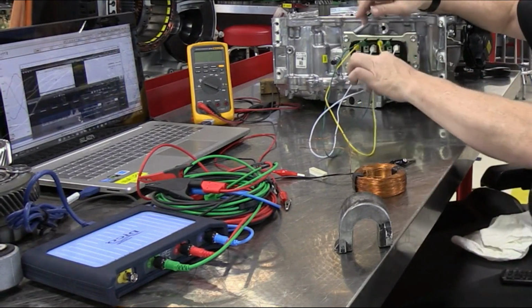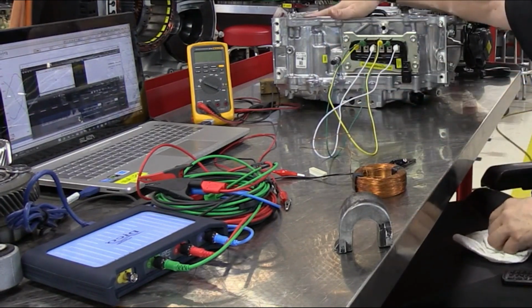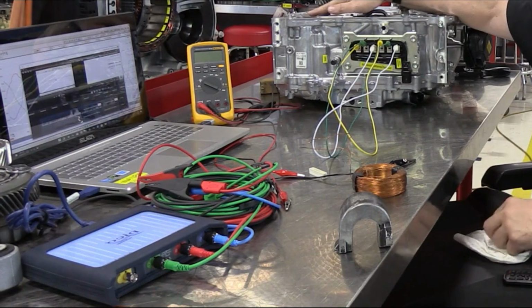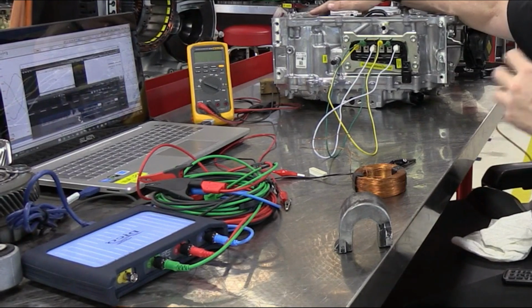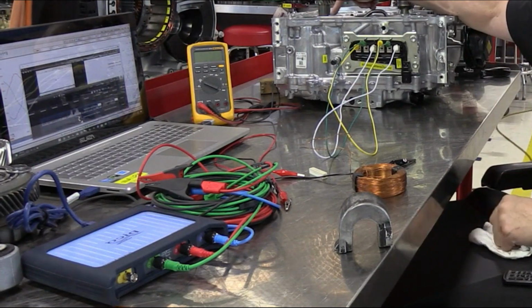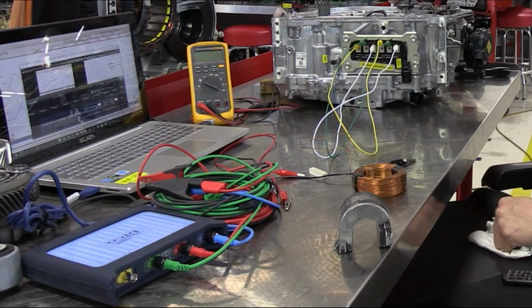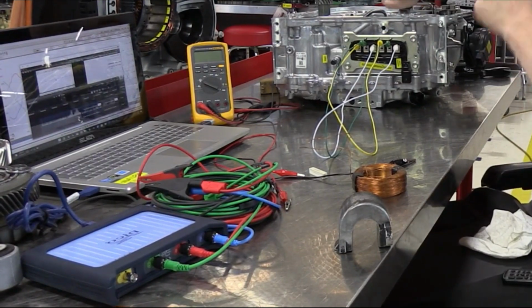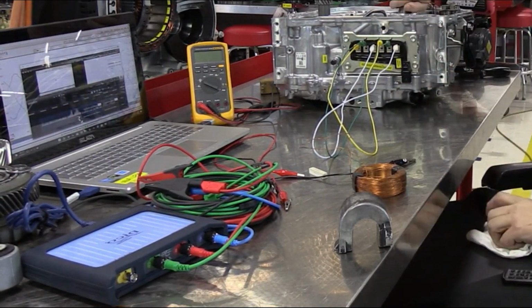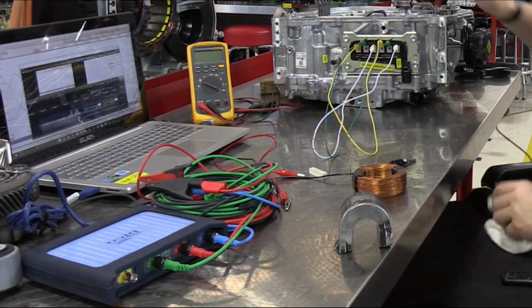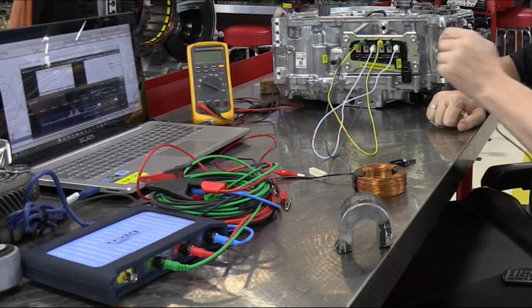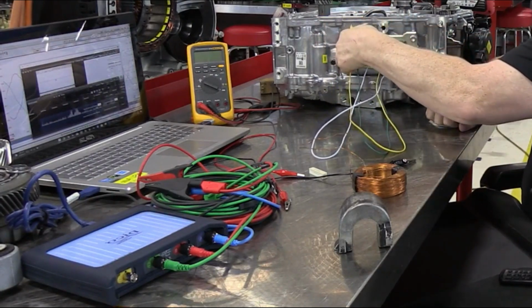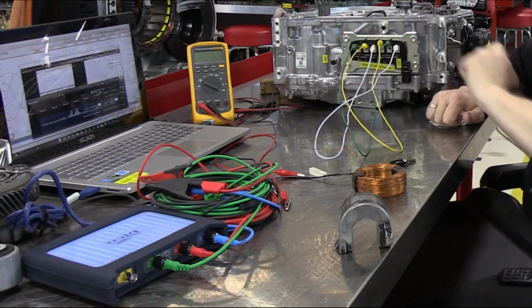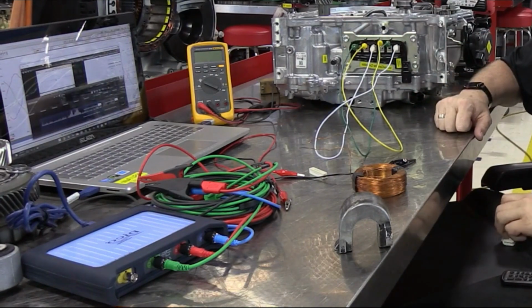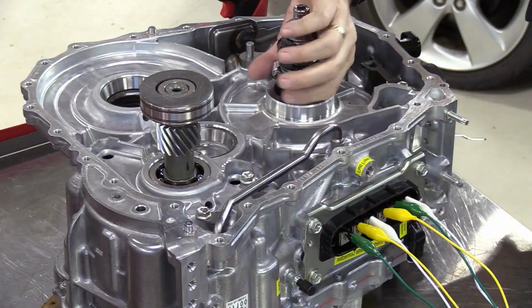Normally, when the stator windings are shorted together, the electrical impedance of the motor drastically reduces. The impedance of the motor winding includes both resistance and inductive reactance. In normal operation, this impedance limits the current flow to a safe level. However, in a short circuit condition, the impedance is effectively bypassed, leading to an almost direct connection between the power source and the windings. The current flow becomes limited only by the resistance of the copper winding, which is very low, leading to an enormous surge in current, typically measured in multiples of the motor's nominal current, often 10 to 100 times higher.